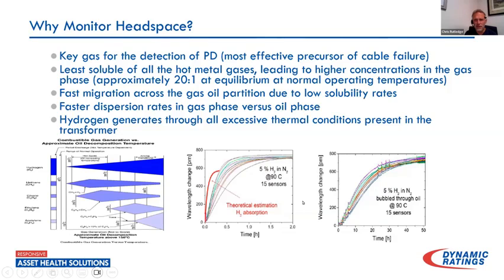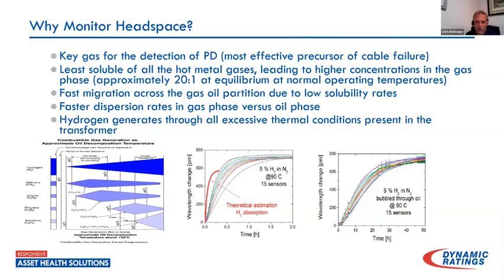This actually came from another company but I like to include it because it verified what I had seen in my own testing. Looking at the chart in the middle — 15 hydrogen sensors installed in the gas phase, 5% hydrogen and nitrogen base at 90 degrees C, pretty high solubility for hydrogen at that temperature — they reached max absorption about one hour's time, about what I was seeing. Then they also did sensors in oil for comparison and in the same experiment you can see it's over 50 hours before really reaching equilibrium, with a wider, less consistent dispersion of the gas.